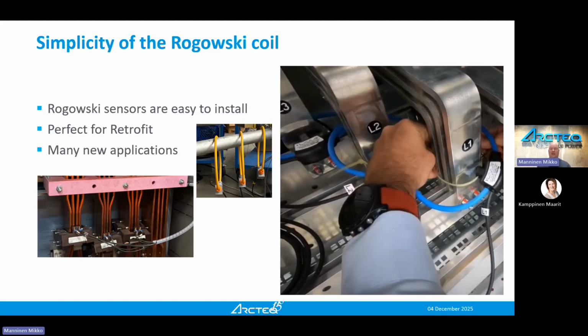I know cases where ArcFlash retrofit projects have been postponed because current transformers needed an extra panel since they didn't fit into the existing compartments - they even built an extra panel and extra bus bars only for that purpose. So that is many times actually a bigger job than the actual ArcFlash sensor installation, which is fairly simple.